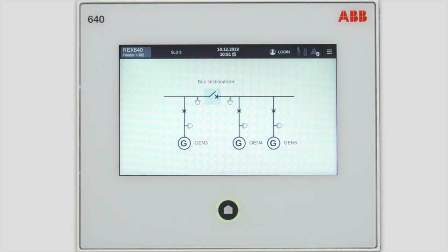On this single line diagram, you have three generators and a bus sectionalizer breaker. The breaker divides the bus bar, leaving generator number three and generators four and five on different sides. The generators in this example are supplying local loads without connection to the grid. The target is to close the bus sectionalizer breaker in a synchronized manner.